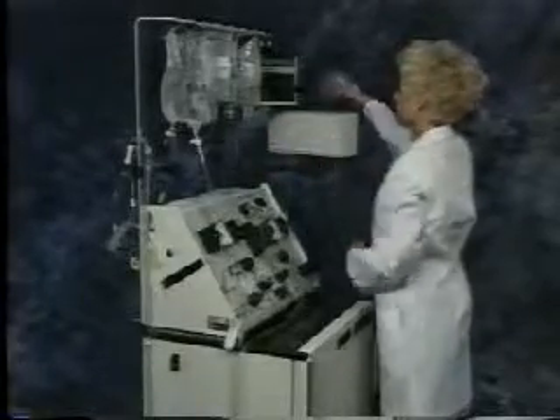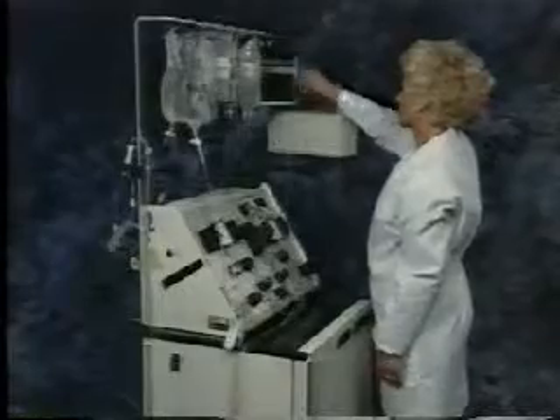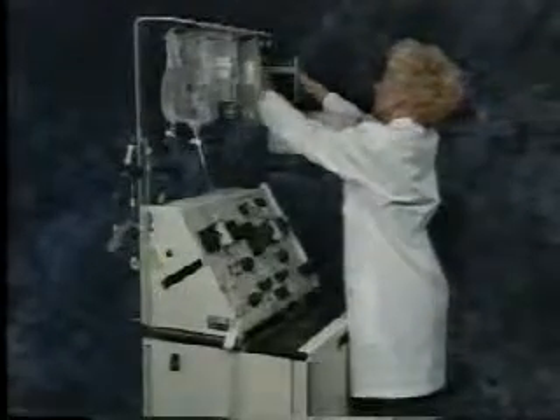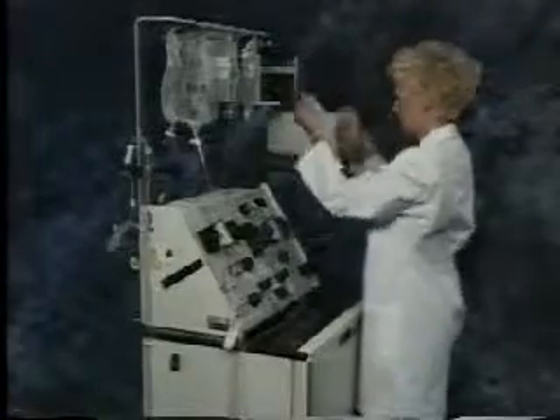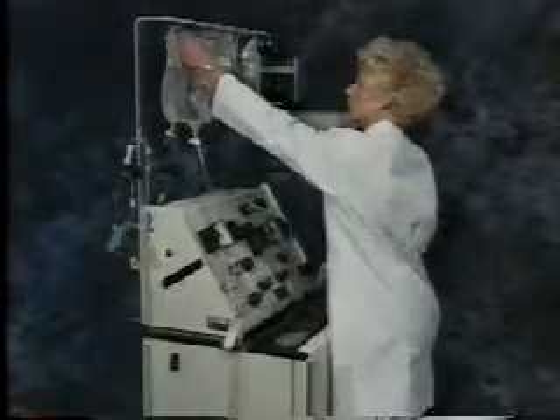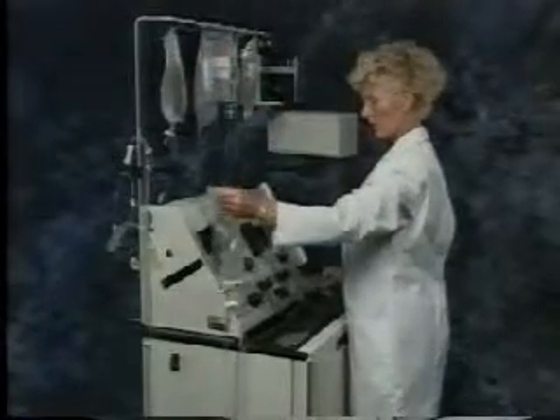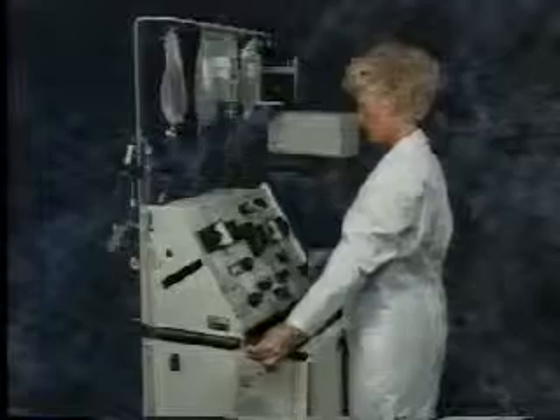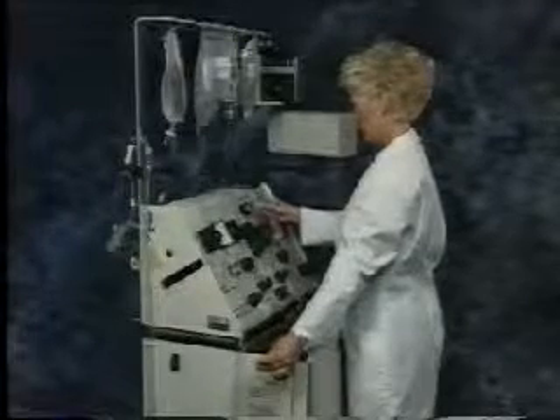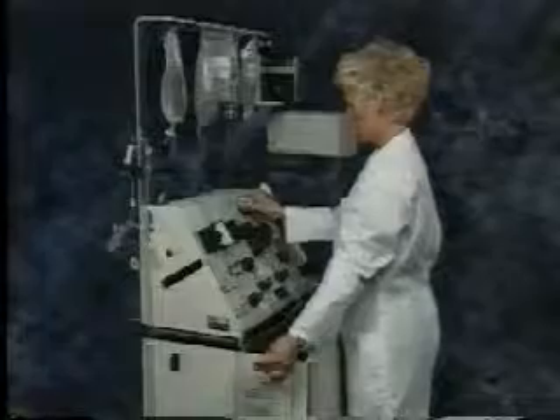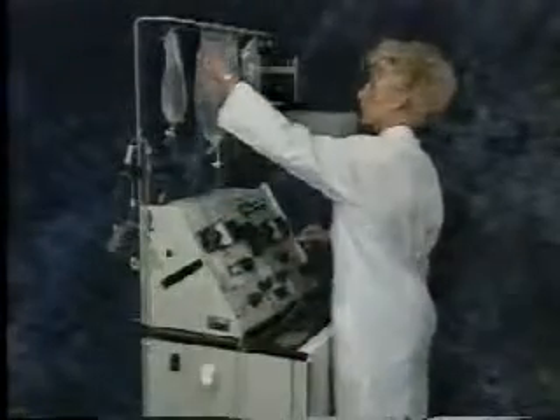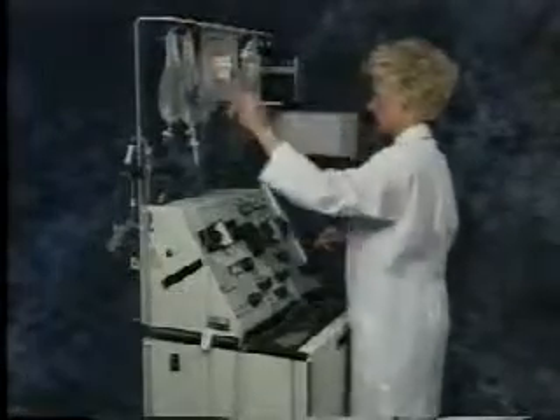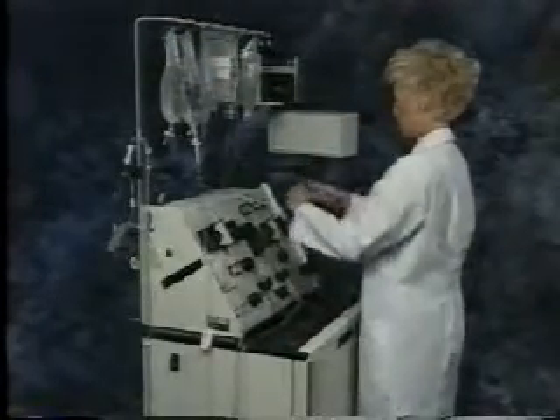Remove the single needle bag from the return flow controller and place it on the centrifuge cover. Lower the saline container until it is even with the centrifuge cover. Watch the diaphragm in the sensor and wait until it is properly positioned. While keeping the saline bag lowered, load the return pressure sensor. Then rehang the saline bag. Return the single needle bag to the return flow controller, making sure to crank clockwise all the way back to the prime position.